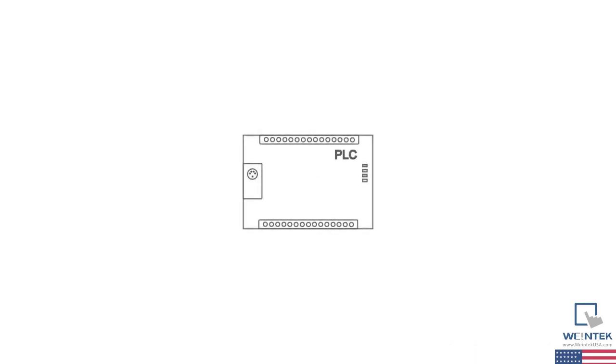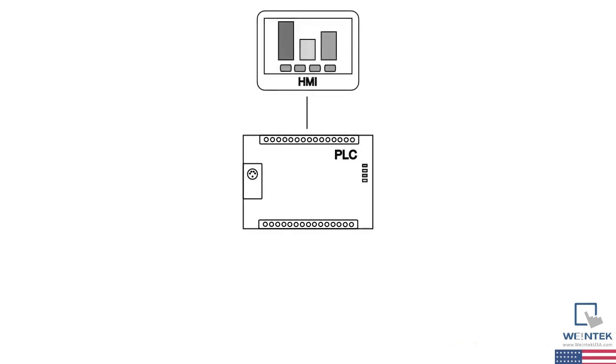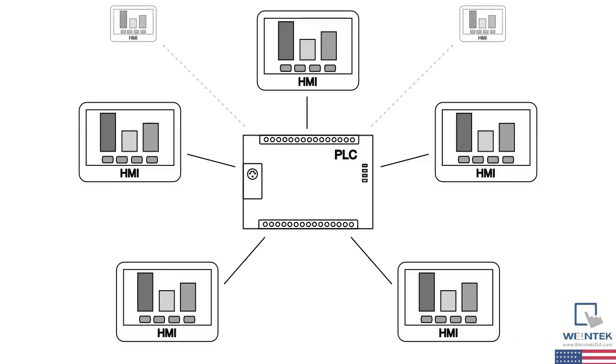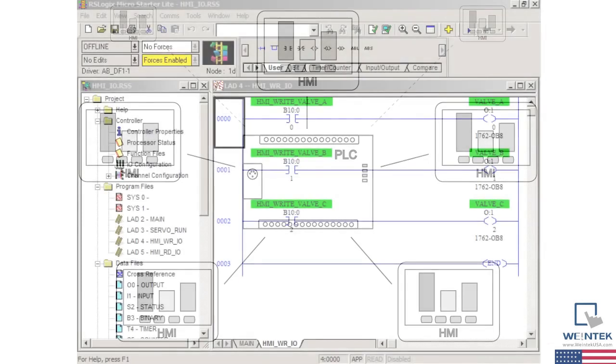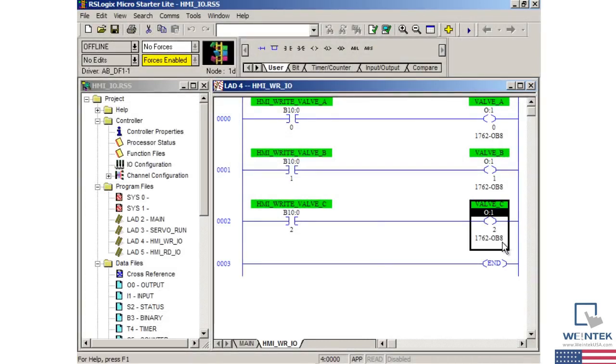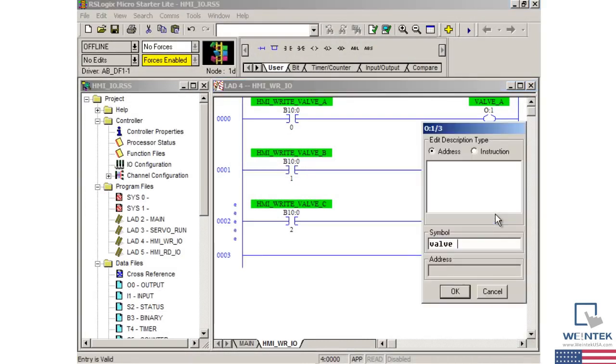The development and maintenance of a system is determined in large part by its design and its documentation. If we take a haphazard approach to how we interface the HMI to the PLC, we may end up making more work for ourselves or others down the line. If we want to make even minor changes to the PLC program, which happen to affect the areas accessed by the HMI, then the HMI or HMIs will have to be reprogrammed as well. And hopefully, the person changing the PLC program will be aware of the affected HMIs, both local and remote. However, if we've implemented an HMI interface table in the PLC, there may need to be no change to the HMIs, only a remapping of the interface table in the PLC to the various PLC data areas affected.